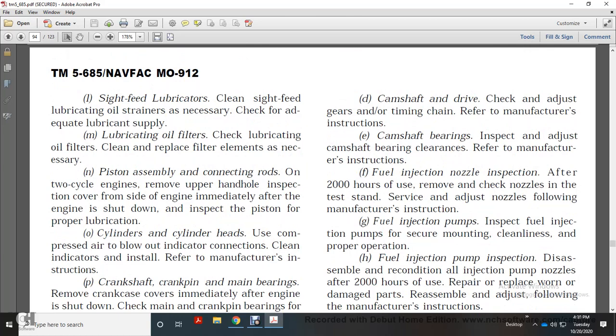Camshaft and drive: check and adjust the gear and timing chain per the manufacturer's instructions. Camshaft bearing: inspect and adjust the camshaft bearing, and clean per the manufacturer's instructions. Fuel injection nozzle inspection: after 2,000 hours, remove and check the nozzle on the test stand, and test the nozzle following the manufacturer's instructions.